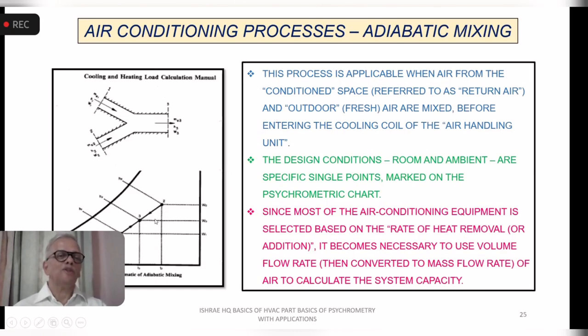So that is the commonly used process. And here you see the psychrometry. The two streams are mixed, the same example as previous. This process is applicable when conditioned air, the return air, is mixed with outdoor air before entering the coil in the air handling unit. So the mixture of the outdoor air and the return air will go to the air handling unit. The desired conditions are plotted as single points, and then depending on the percentage, as we said, the mixture point will be determined.